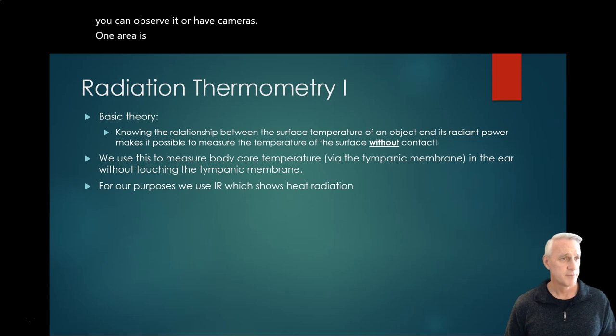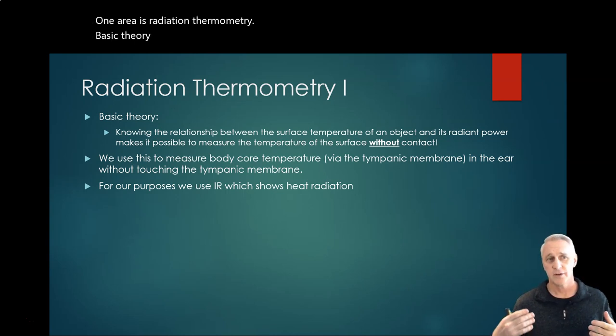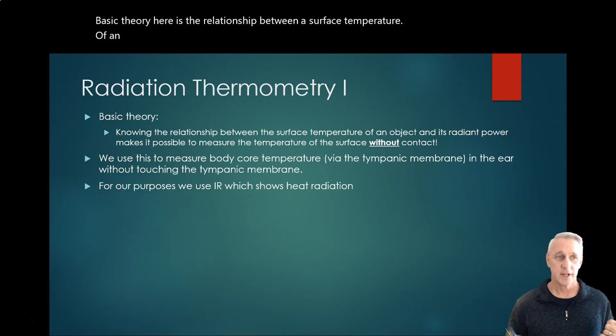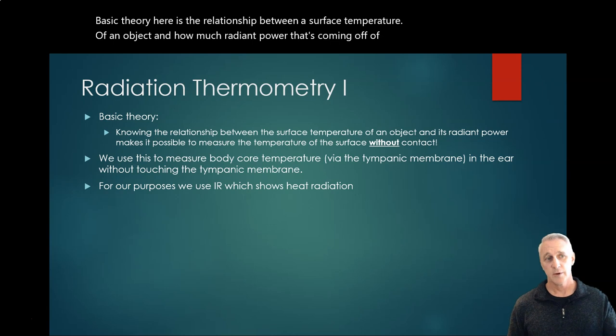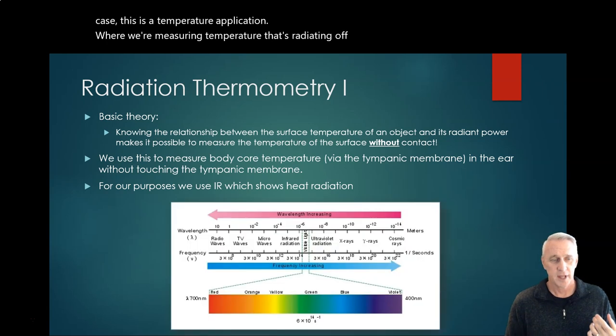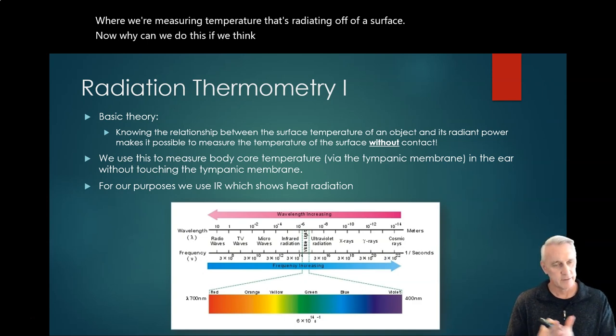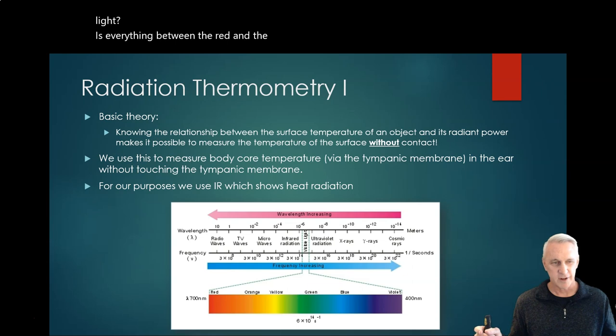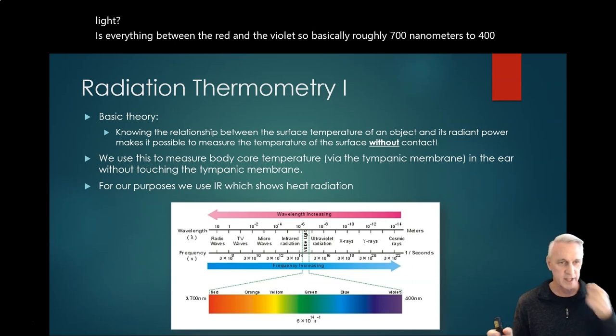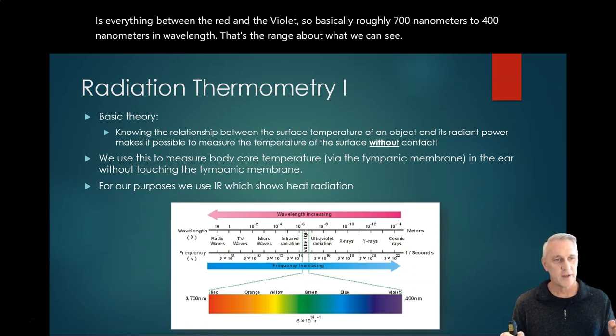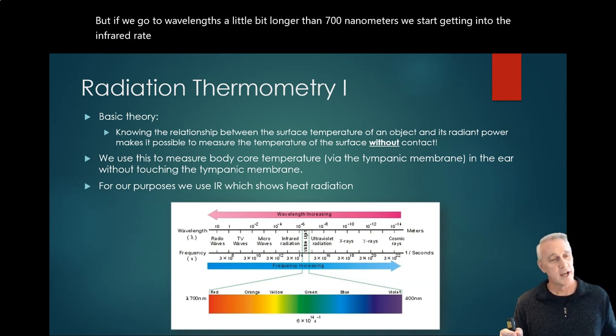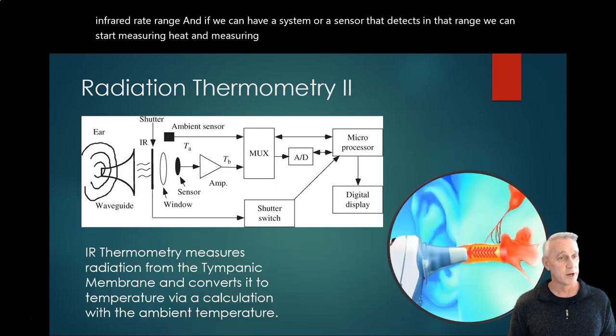One area is radiation thermometry. The basic theory is you know the relationship between a surface temperature of an object and how much radiant power is coming off of it. This is a temperature application where we're measuring temperature radiating off a surface. Visible light is everything between red and violet — roughly 700 nanometers to 400 nanometers in wavelength. If we go to wavelengths a little bit longer than 700 nanometers, we start getting into the infrared range. With a sensor that detects in that range, we can start measuring heat. So it's IR that we're actually measuring in this case.